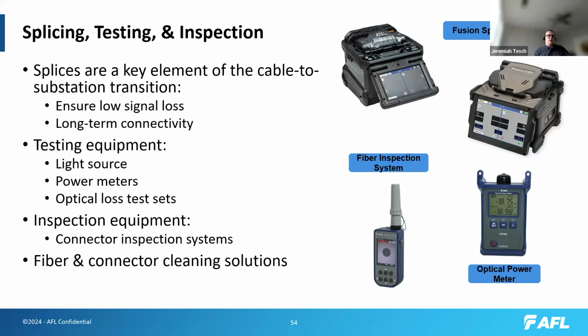That way you have data points between manufacturing, shipping, storage, warehouse handling, and so on, showing the cable was in good condition at certain points before installation. So if anything happens during installation, you know the last point at which it was in good condition.